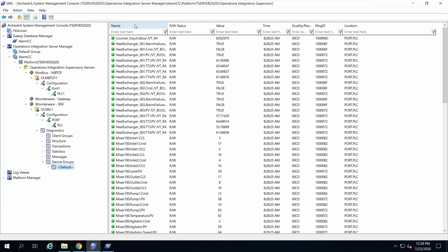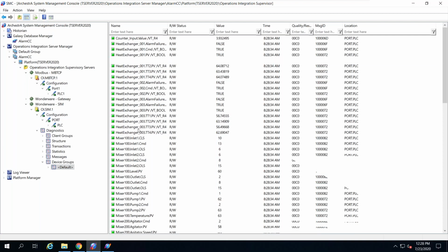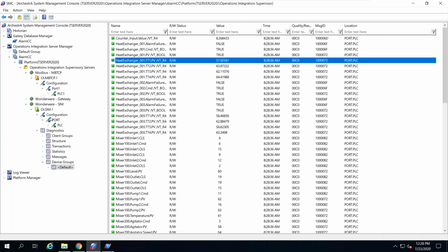Open it here. So if you find that this object is missing, doesn't exist here, that means there is a miscommunication between the object and the server. Could be the server, you have to check the configuration of the server itself. If it's green, that means it's still connected. It is connected, it's fine. But if it's green and there is no value, in this case, you have to check the cybersecurity. Maybe it blocked the OPC configuration.